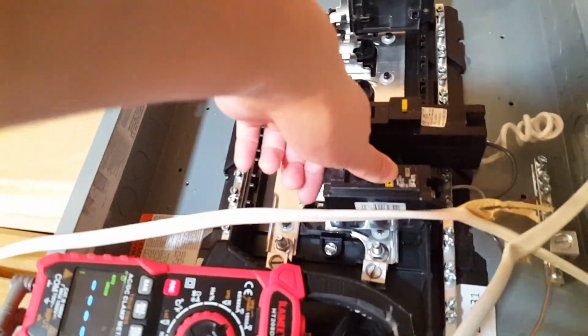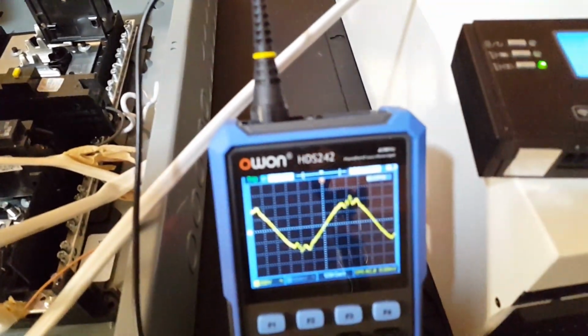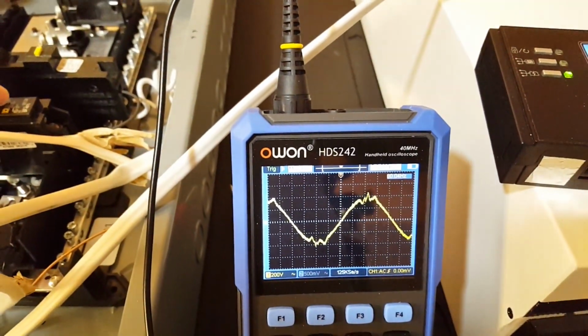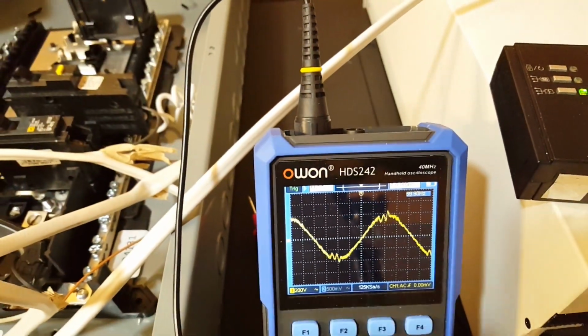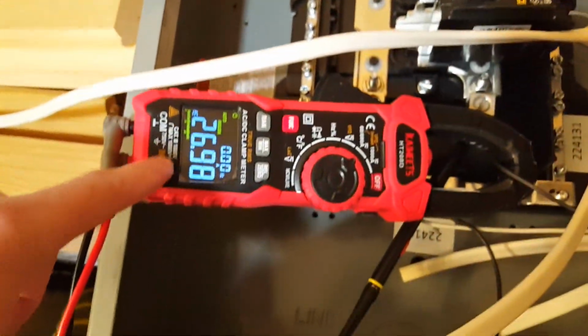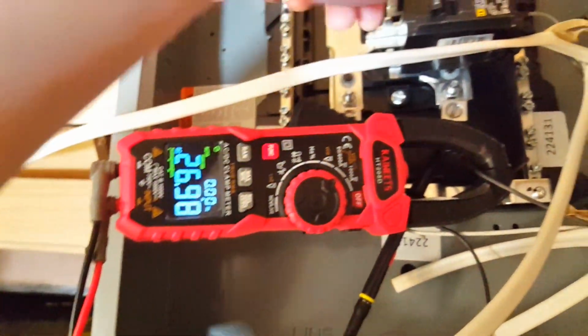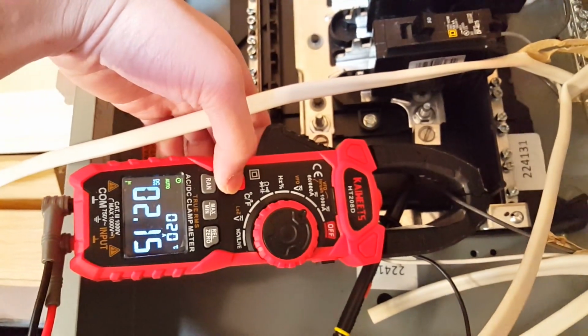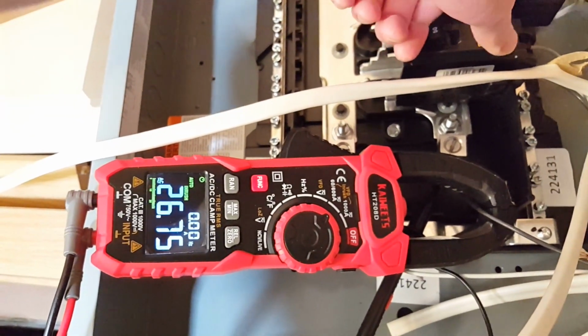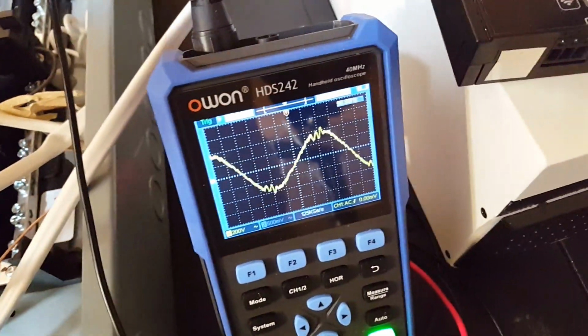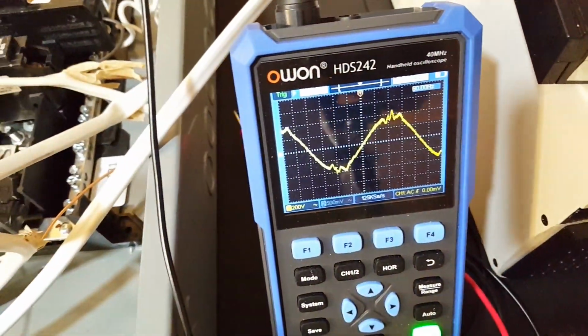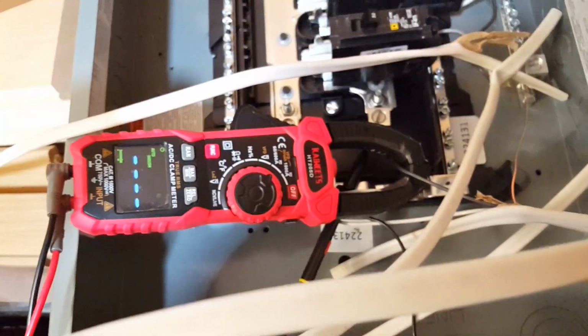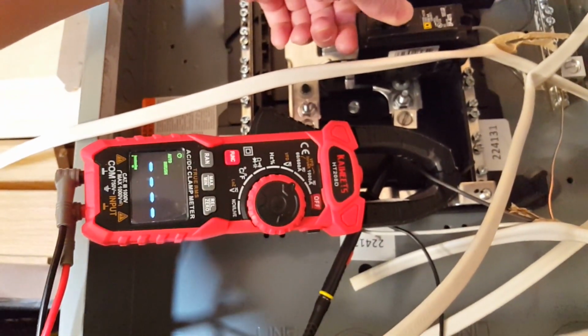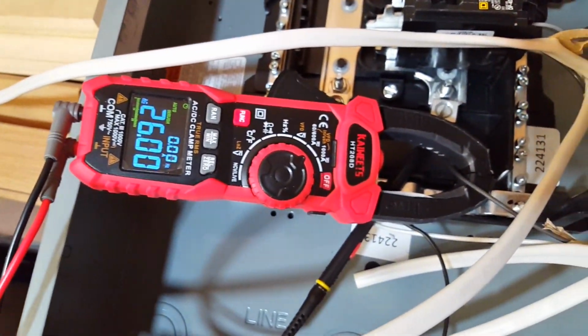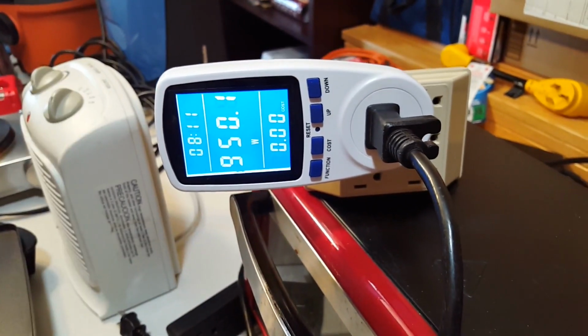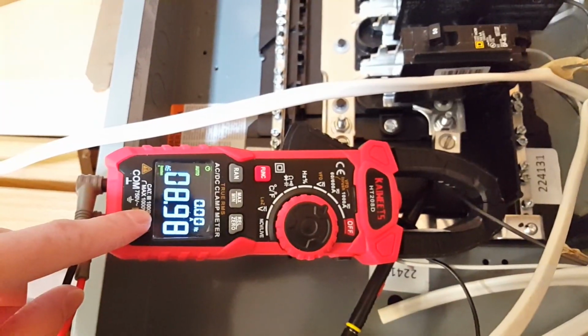We're measuring inrush amps. We're currently still in battery mode, and we'll look at the waveform and see if it changes under load with the surge. So, yep, you see a little bit of a ripple there. The AC surge amp is 26.98. Let's try it again. One more time. 26.75. There's the waveform. If you want the running wattage, one last time for the surge test for the shop vac. 26 surge amps. The wattage is 950 watts. The running amps, 9 amps running.